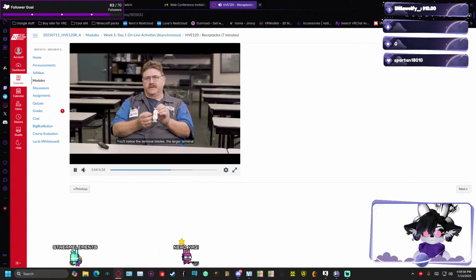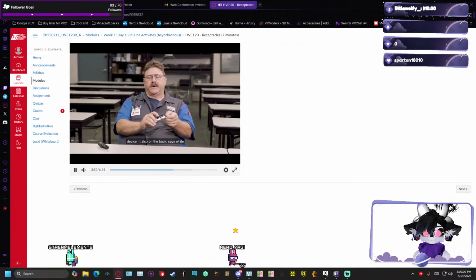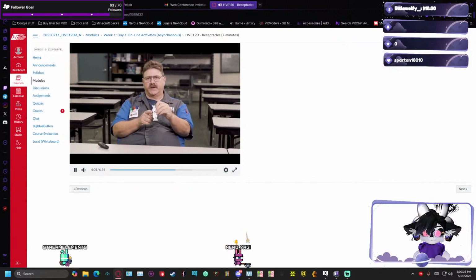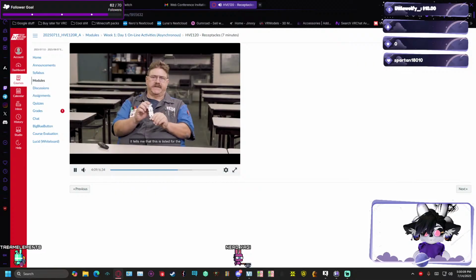On the front of the receptacle, you'll notice the terminal blades. The larger terminal is on the silver side, so that would tell me that's the neutral side of the device. It also says white conductor on the back of the device. So 3 places it tells me that this side of the device is designed for the neutral conductor. Again, the smaller terminal, the brass screws, and hot written on the back are 3 places it tells me that this is listed for the hot conductor, the line, the power.